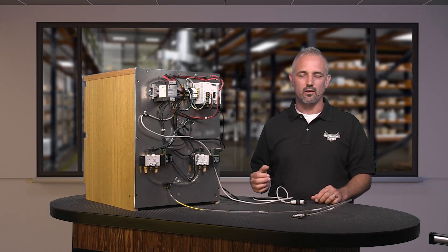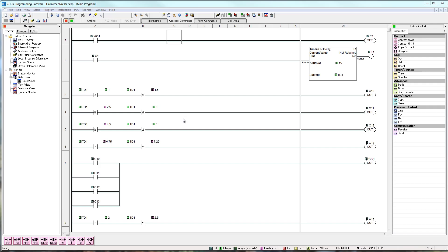Last is programming the PLC. There are many ways of programming what our end goal or result is. And I won't go into great detail on programming but simply show you how I program this system with a few lines of code. We offer detailed programming videos and training videos here at AutomationDirect and if you need further instruction we have resources for that. The code I used says that if the sensor is triggered and it turns on an input X1, this will in turn set an internal bit which we assign to C1. When C1 is on and set, we start a timer T1 and start it timing. This timer times in seconds up to 15 seconds.